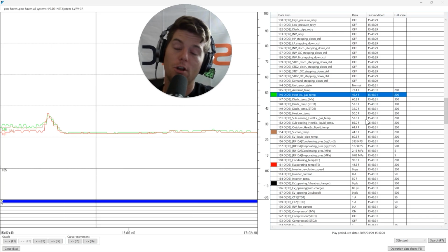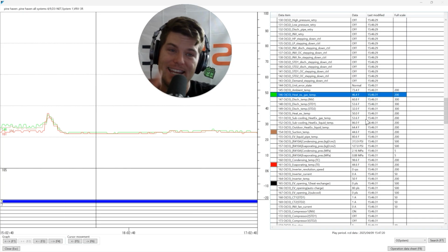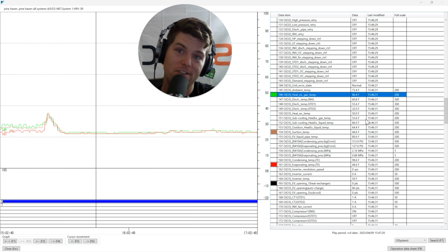The VRV3 unit will try to send hot gas to that module, but if you have that valve shut and you have the liquid line shut and the suction line open so the gas can be pulled out of the module over time when it equalizes to ambient, you'll be fine, right? So you can lock out VRV3 modules and do exactly this if you have refrigerant bleed by. And again, this is an easy test you can do on site where you go and actually physically close the liquid line on the unit to make sure that your diagnosis is solid. And that's how you stop refrigerant bleed by on a sub-module like this where you're losing compressors at a constant.